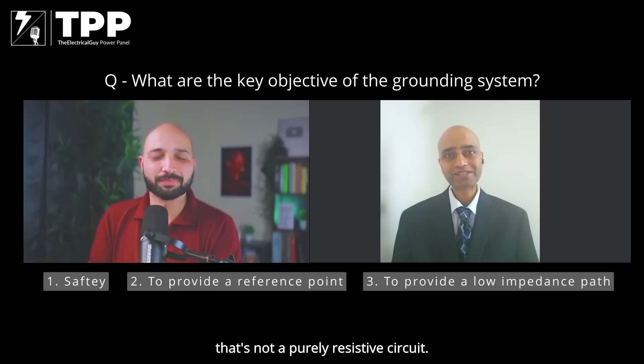The objective of the grounding system is, of course, safety first, that's the underlying one. Then there's making sure our system, the whole power grid, has a reference point for voltage stabilization. At the same time, it provides low impedance, I say impedance because inherently there is inductance in the power grid since it's not a purely resistive circuit, so the impedance part matters to the grid. So those are the three objectives.